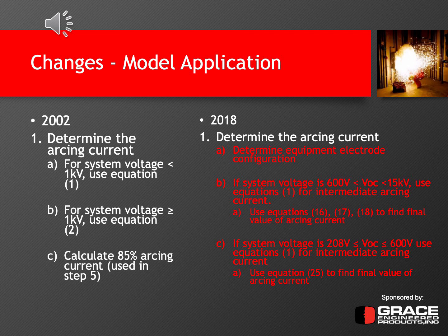So looking at 2002, basically, step 1 is determine the arcing current, and in 2002 there's 3 things you need to look at. For system voltages less than 1 kV, they say use equation 1. For system voltages greater than or equal to 1 kV, use equation 2, and then also calculate 85% of the arcing current that you determine in steps A or B, and that'll be used in step 5.